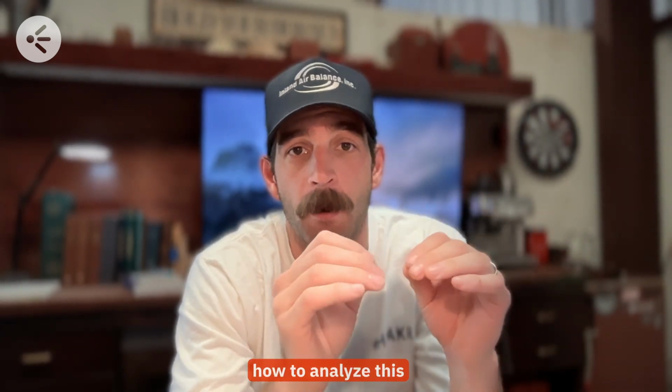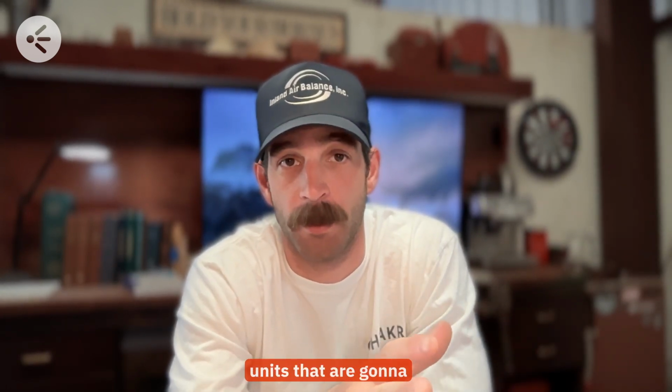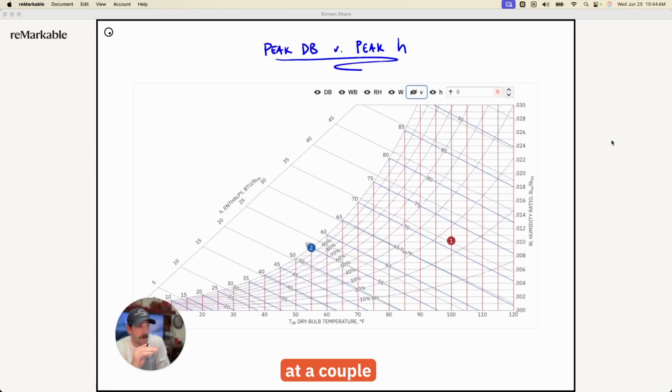I'm going to explain how to analyze this and how it affects your coil sizing, especially for DOAS units that are going to bring in 100% fresh outdoor air. Let's take a look. To demonstrate this, we're going to look at a couple different outdoor air conditions and assess the impact on a coil. So the first condition we're going to look at is the peak dry bulb condition.